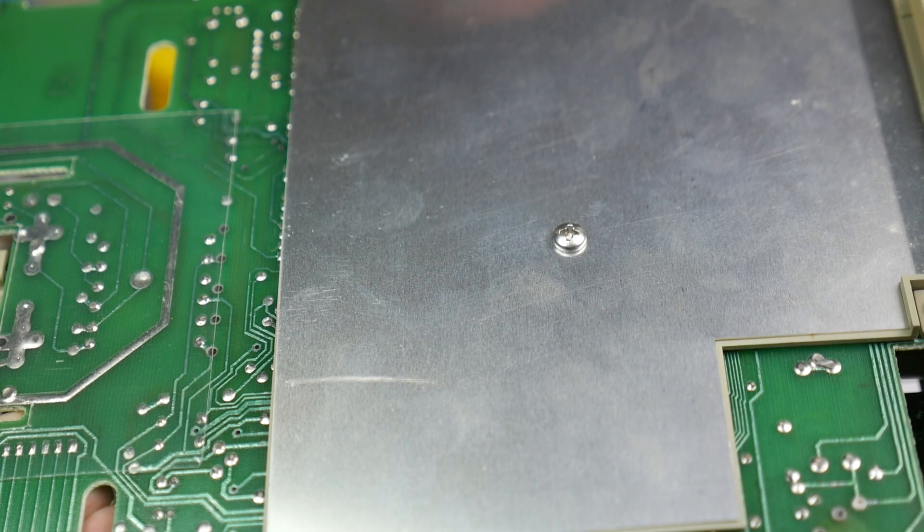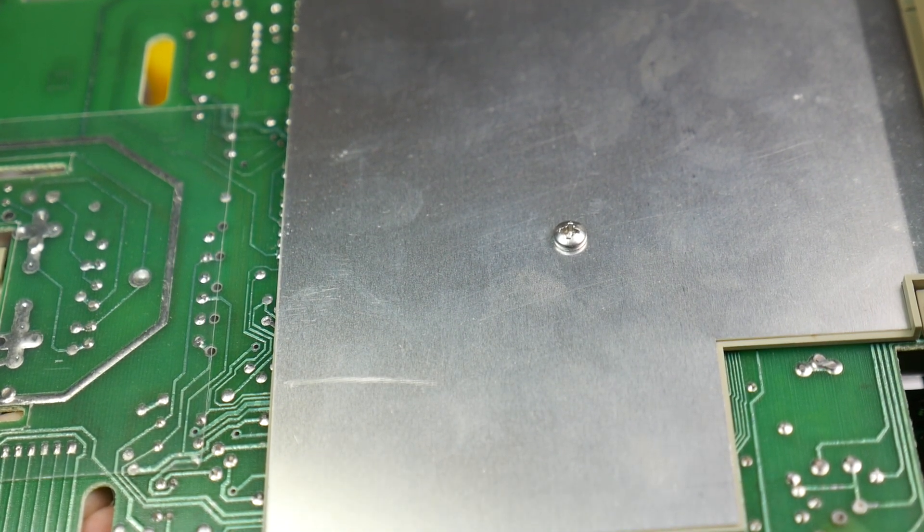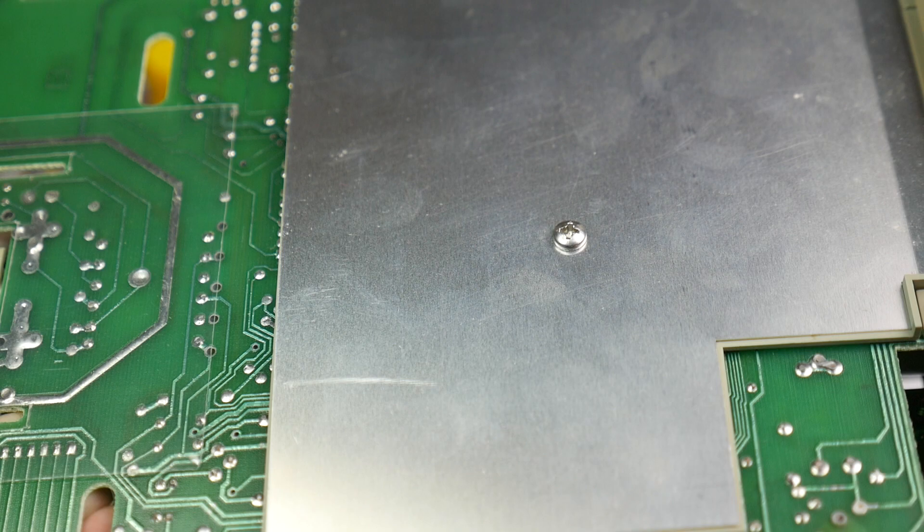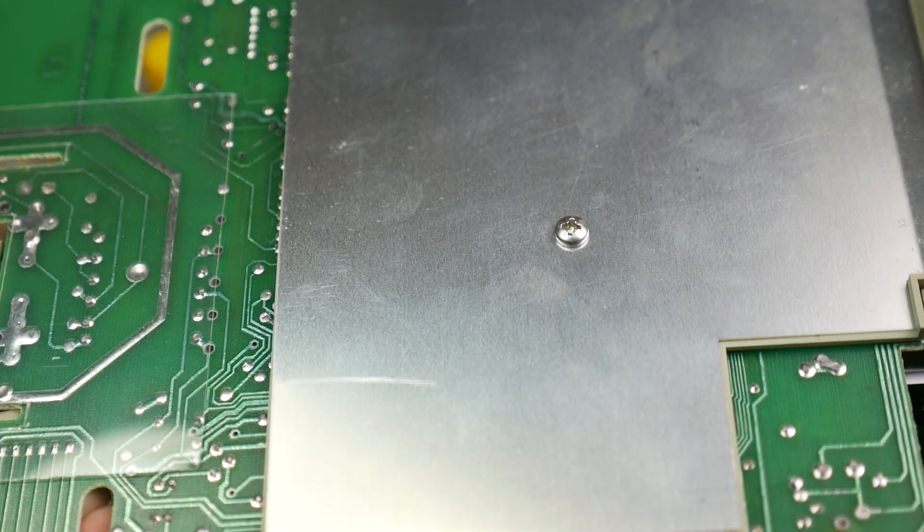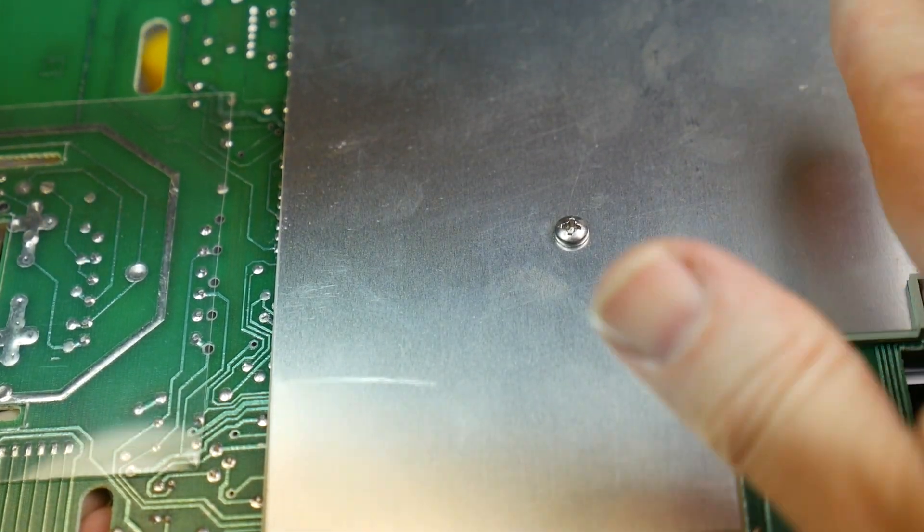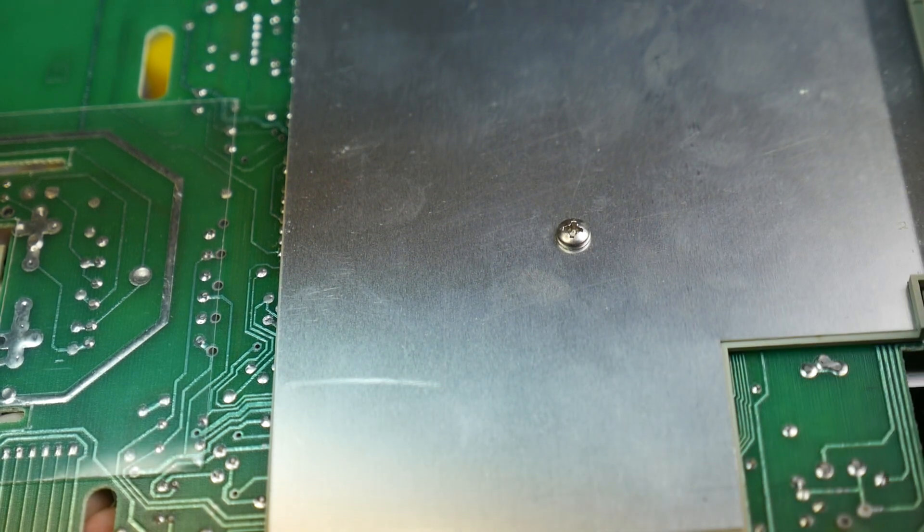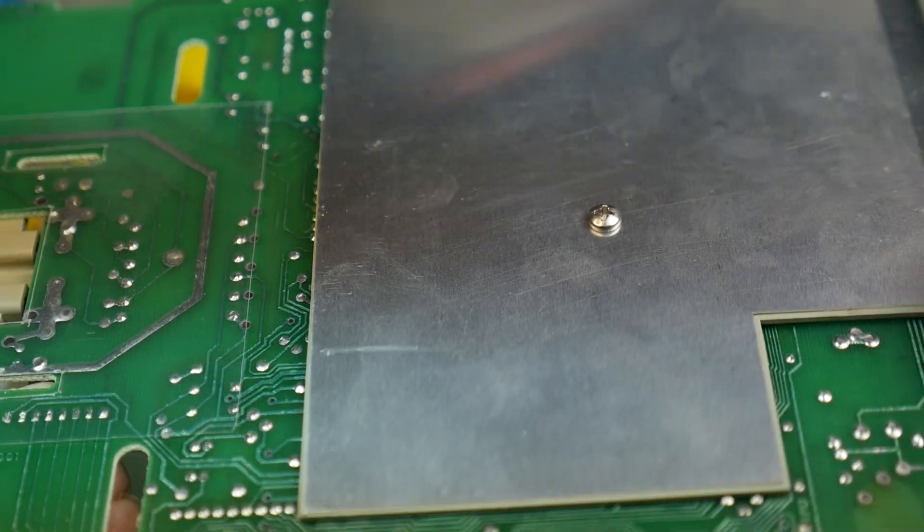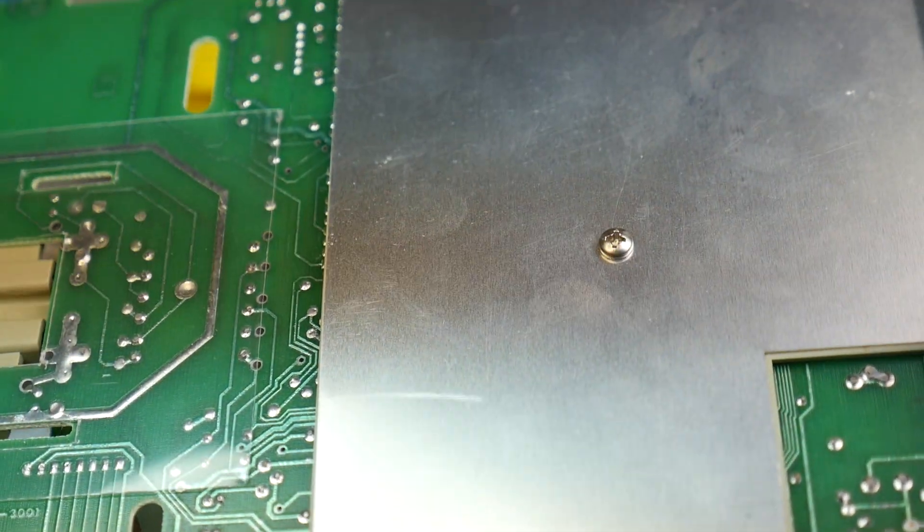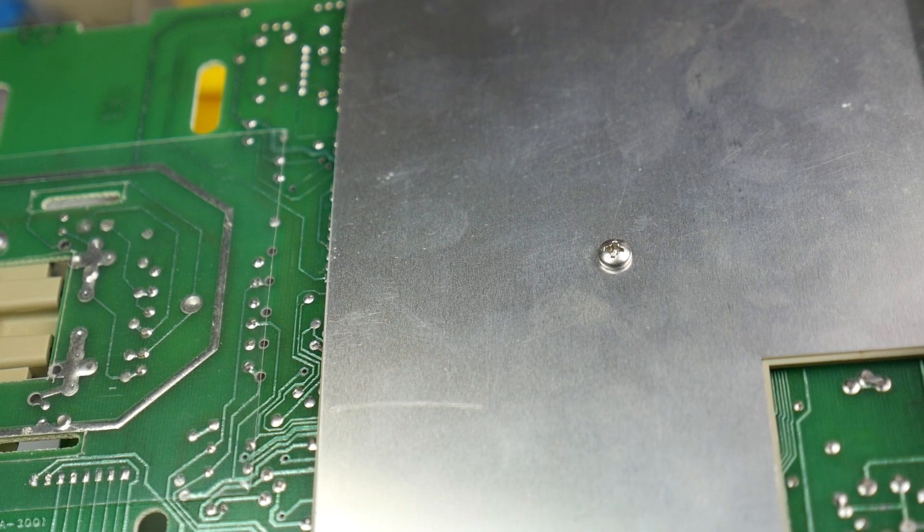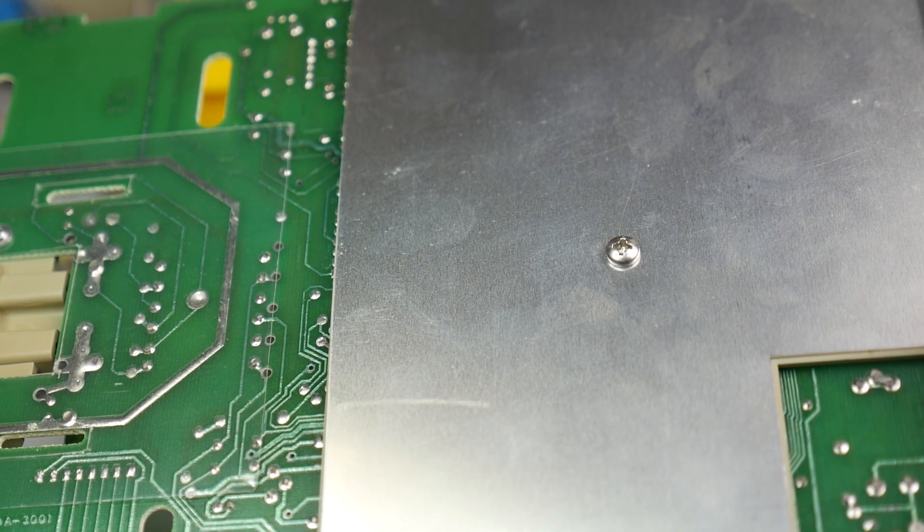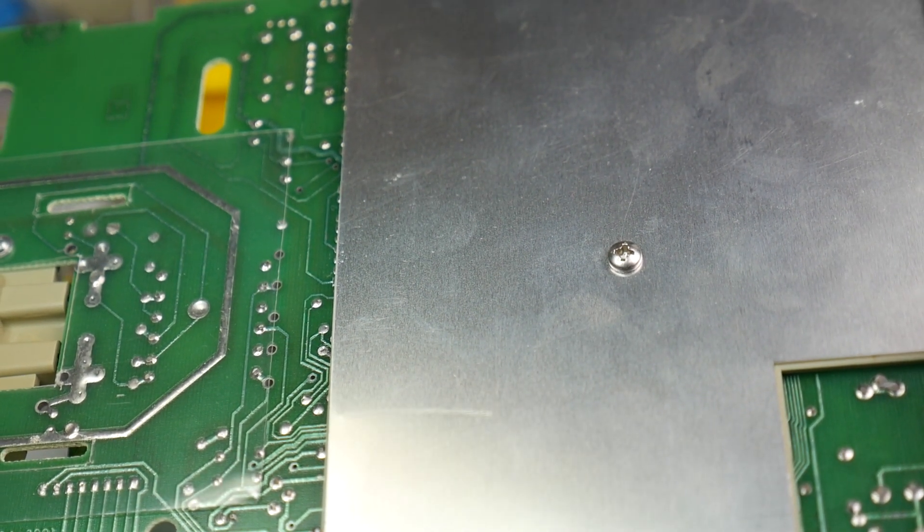There's a big metal plate. It's only thin metal. This is a screen. It's grounded in the middle—earth in the middle there. Remember, the outer casing is just a plastic sleeve. So the whole thing needs some screening, and that's what does the screening. This is the sensitive analog input circuitry, screened and protected from stray fields influencing your measurements.